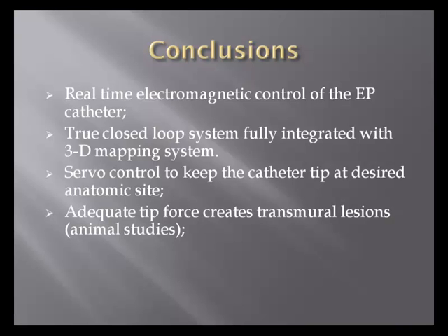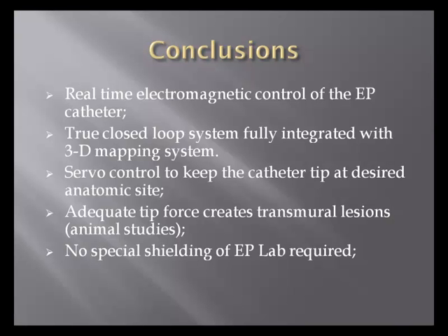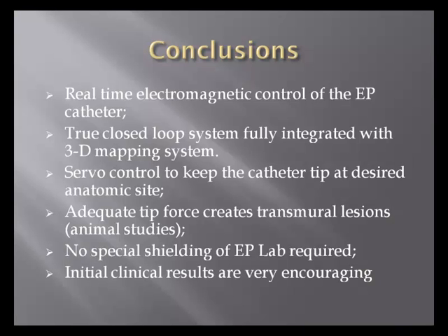Adequate tip force creates transmural lesions, as I showed you in animal studies, and no special shielding of the EP lab, as Josh told you in great detail. Initial clinical results are very encouraging, and we're now undertaking an ablation protocol.